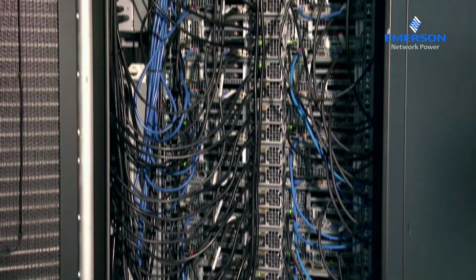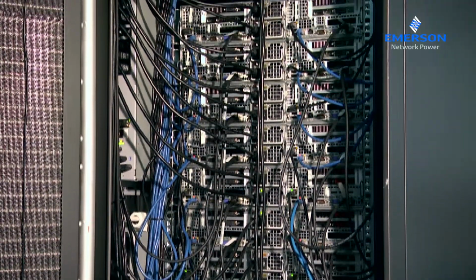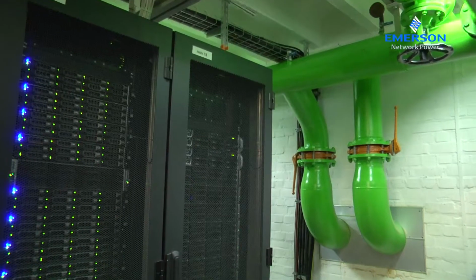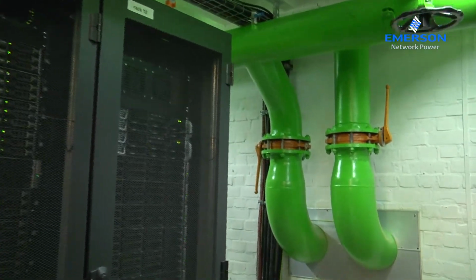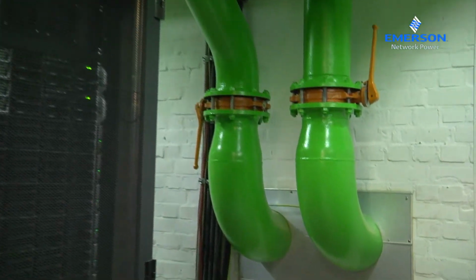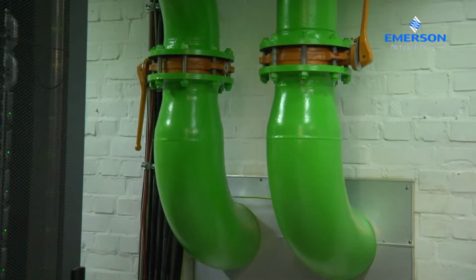The heat exchanger is designed in a rather smart way, such that it produces almost no back pressure. In numbers, we're talking something like 20 Pascal, which also means the rack doesn't have to be perfectly sealed, particularly areas where you feed cables in and out are never perfectly closed, doesn't matter. Consequently, the entire system is very simple and easy to maintain. No regulation of water flow or airflow in any form, we just pump the water through the heat exchanger.